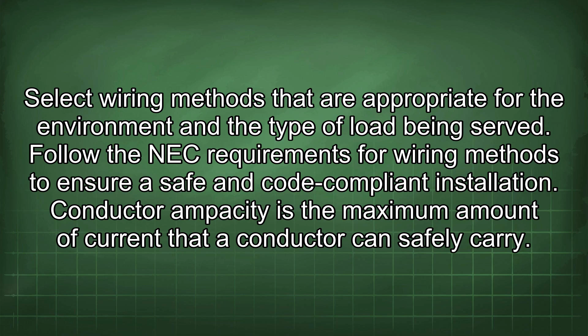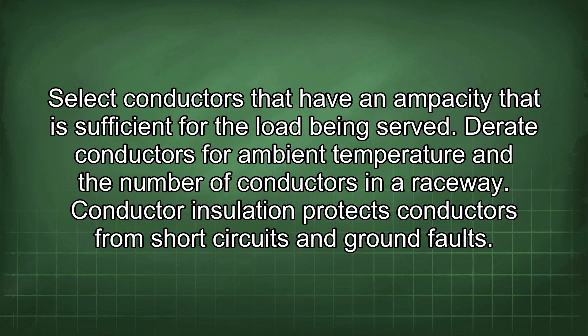Conductor ampacity is the maximum amount of current that a conductor can safely carry. Select conductors that have an ampacity sufficient for the load being served. Derate conductors for ambient temperature and the number of conductors in a raceway. Conductor insulation protects conductors from short circuits and ground faults. Select conductors with insulation that is appropriate for the voltage and temperature of the application.